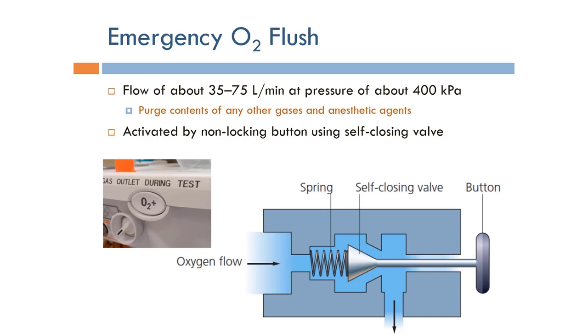It is very important to note that the emergency oxygen flush should never be used when the patient has the breathing circuit connected to them, because it can actually cause barotrauma — damage to the lungs — because the pressure is much higher than what the human body can tolerate.